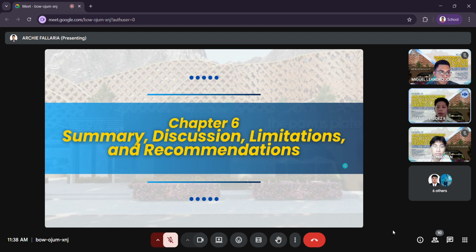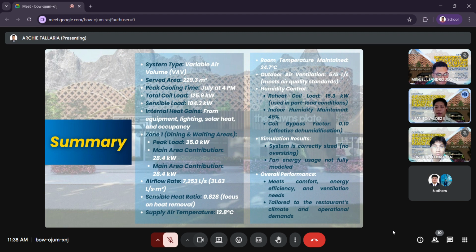Now for the summary discussion on limitations and recommendations in Chapter 6. The air conditioning system, FCU1, uses a variable air volume, or VAV, setup and serves a 229.3 square meter space. Peak cooling occurs in July at 4 p.m. with a total coil load of 125.9 kilowatts and a sensible load of 104.3 kilowatts, driven by high internal gains from equipment, lighting, solar heat, and occupancy. Zone 1, which includes the main dining and waiting areas, has a peak load of 35 kilowatts, with the main area contributing 28.4 kilowatts due to its larger size and equipment use. Airflow is 7,253 liters per second, or 31.63 liters per second per square meter, ensuring effective cooling, and a sensible heat ratio of 0.828 highlights the system's focus on removing heat rather than moisture.